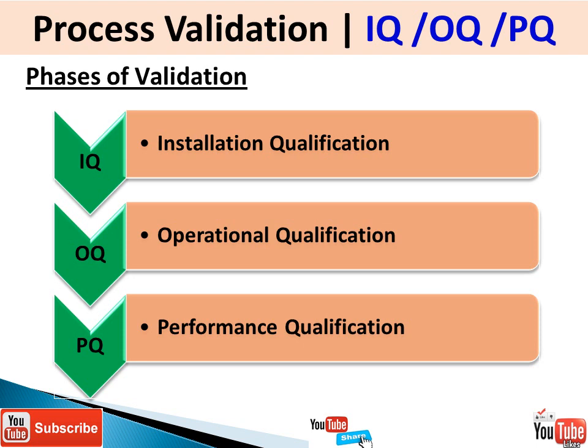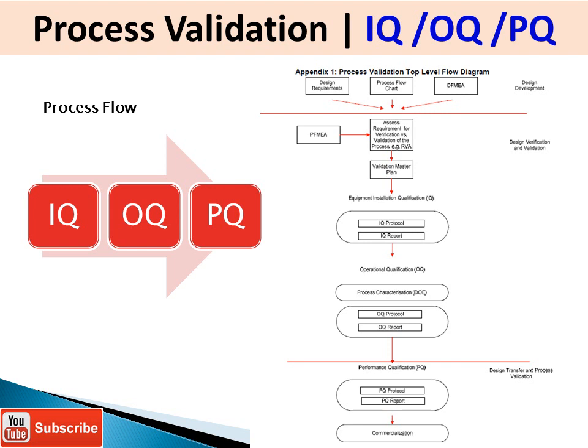The different phases of validation are: the first phase — installation qualification (IQ), the second phase — operation qualification (OQ), and the third phase — performance qualification (PQ). The process starts with installation qualification, for which you need design requirements, process flowchart, DFMEA, and PFMEA. You then create IQ test protocols, perform the testing, and create a report. Next comes operation qualification, where you perform design of experiments to optimize the process, write OQ protocols, and generate an OQ report, followed by performance qualification.